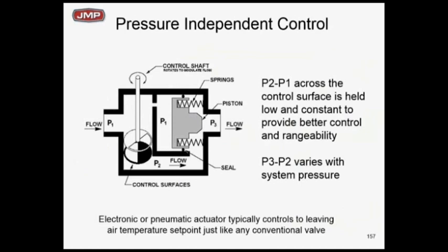How would a pressure independent control valve help you out there? Very simple. A pressure independent control valve is two pieces. This is a typical pressure independent control valve you're looking at. The left-hand side is your two-way valve. P1, P2 is going to stay constant. How in the world can P1, P2 stay constant? Because P1 to P3, the pressure independent control valve, is spring-loaded. It's going to make sure that differential pressure stays the same. The second part, the spring part, is going to make sure the differential pressure from P1 to P2 across your two-way valve stays constant always. Pretty neat trick, but that's what they do for a living.